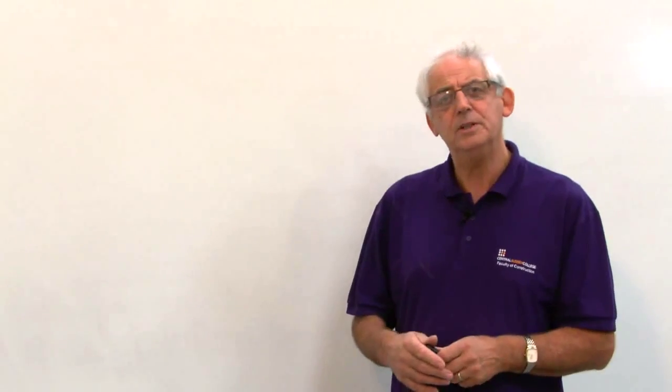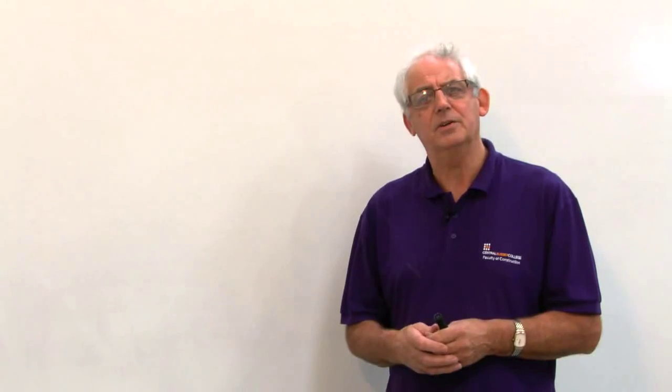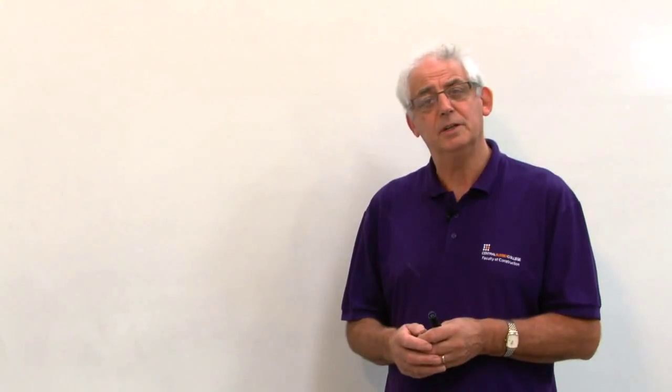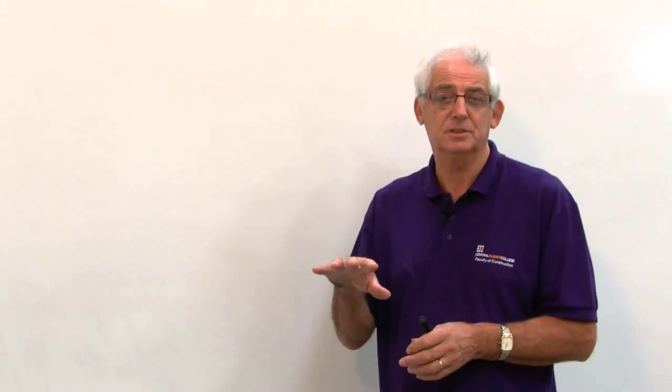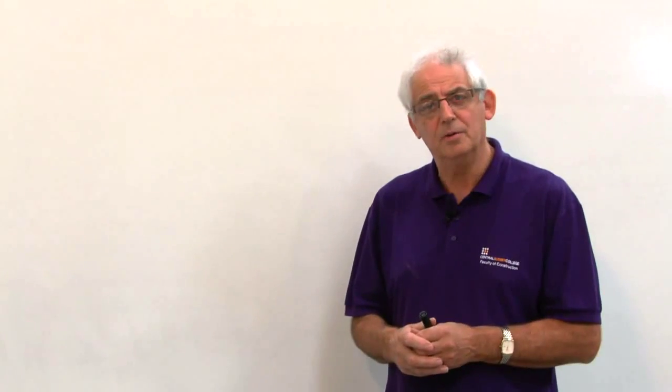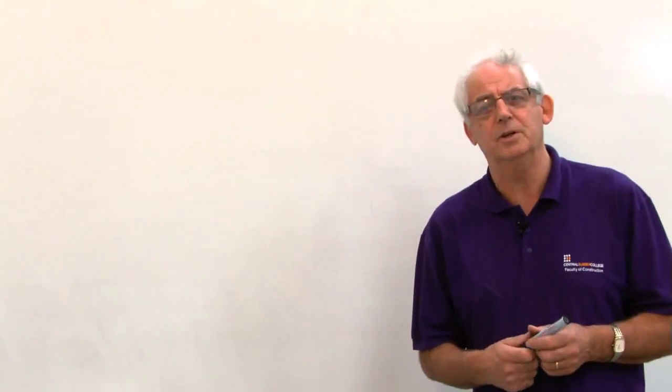Now, of course, if we're measuring separate circuits, we need to carry out a calculation when we finish to make sure that the overall insulation resistance for that system isn't below 1 megohm. Let's just assume, as an example, we've got a situation where we've got 4 circuits.